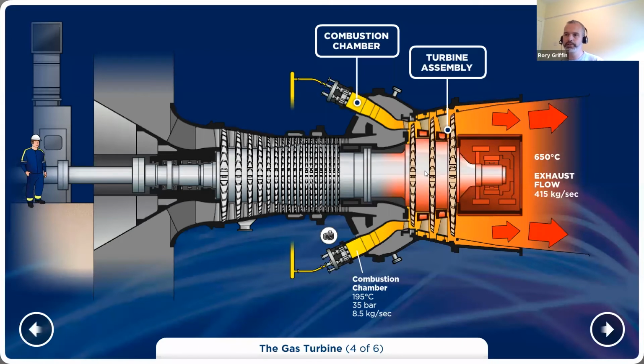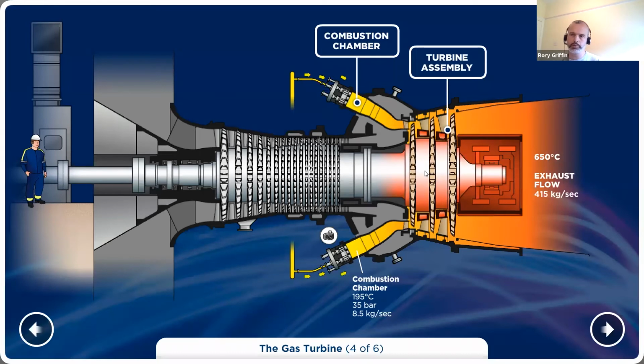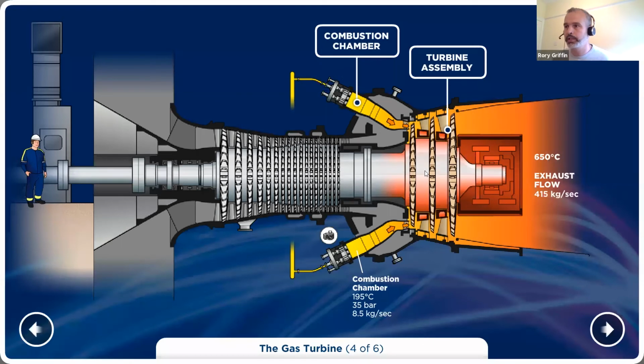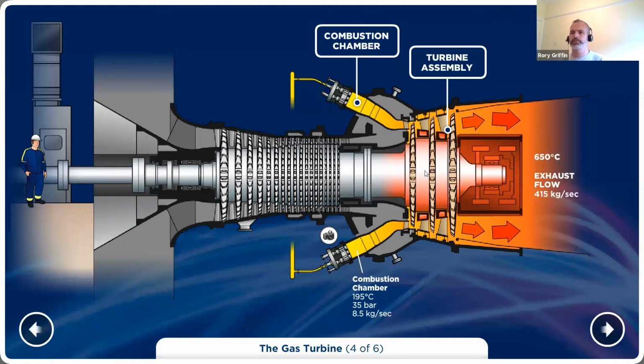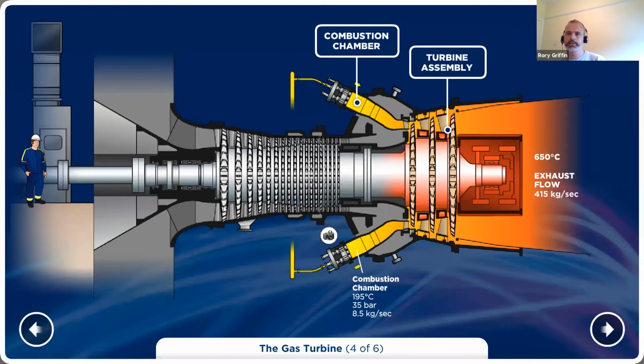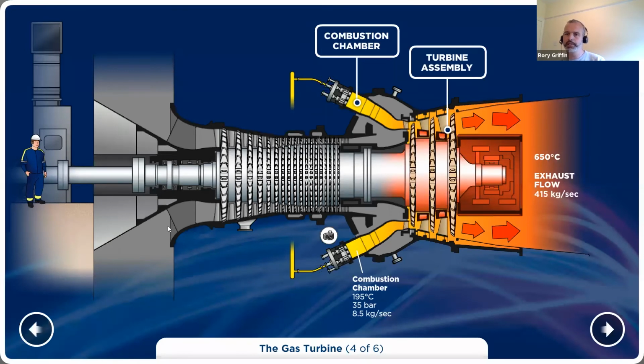And the gas turbine is approximately 2/3 of the power of Whitegate. So it's a 280 megawatt gas turbine. If ambient conditions are favorable, you'll actually get more power out of it. So a gas turbine likes high pressure, kind of low temperature. So those still frosty winter days when there mightn't be any wind, you'll see Whitegate, in commissioning, it actually got up to 460 megawatts. But during the summer, the density of the air is a bit less because it's warmer. That will derate the machine a bit.